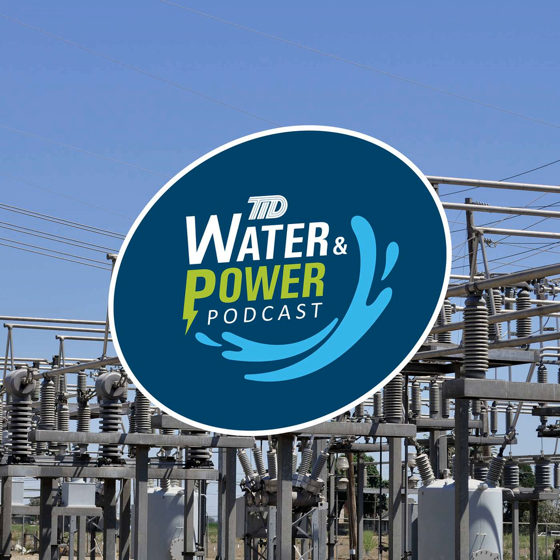So how would you define a tap line? The tap is something that doesn't have a way of really interrupting or protecting itself. We do have some protection at the tap from the transformer—fuses that feed it—but it resides on a line that's protected on both sides with interrupting equipment, so it's kind of at the whim of that line. It may have nothing to do with anything nearby, but if that line needs to go, the station's going to go as well.